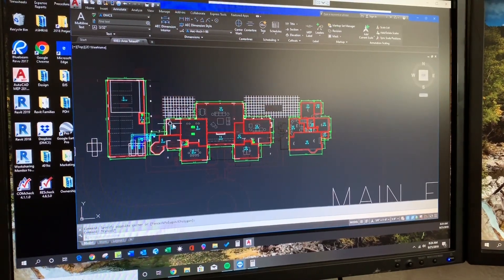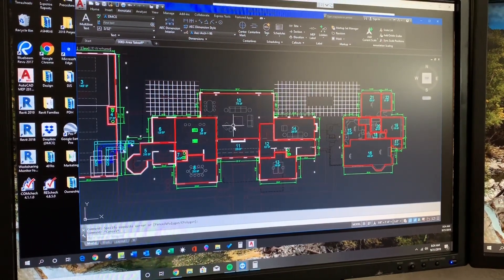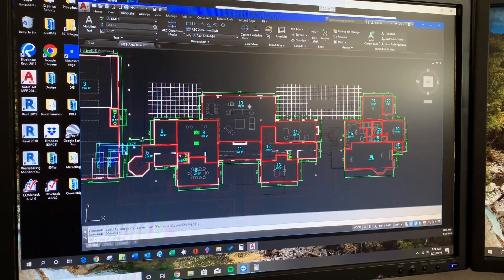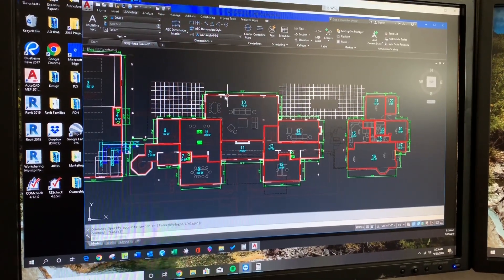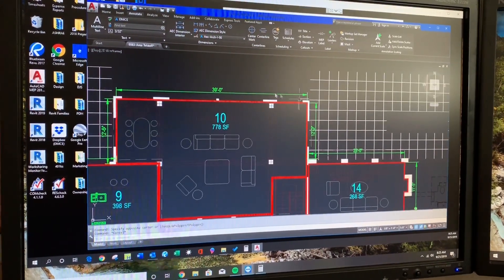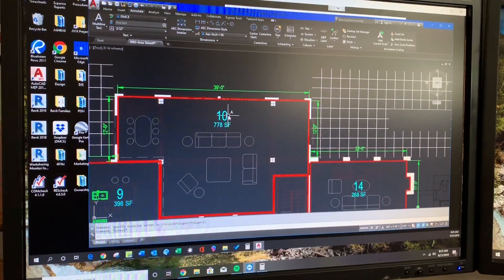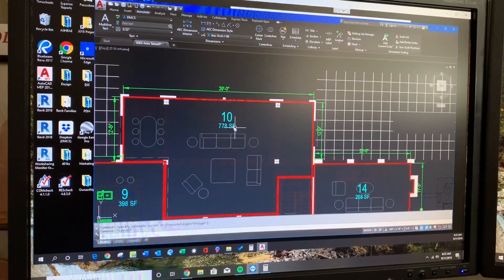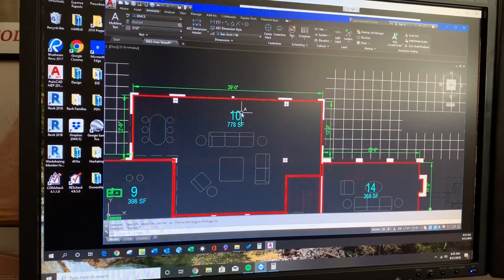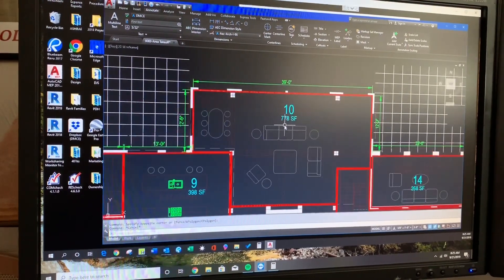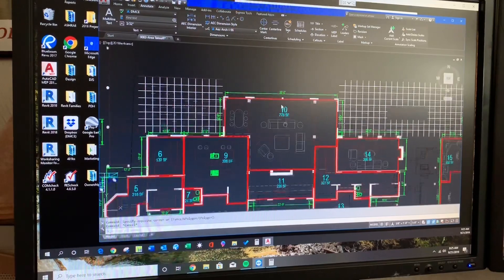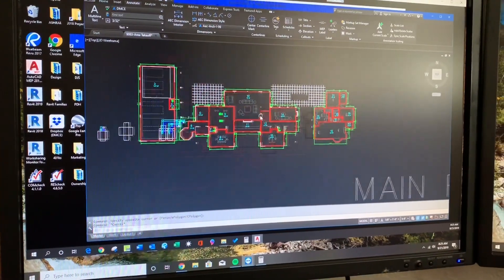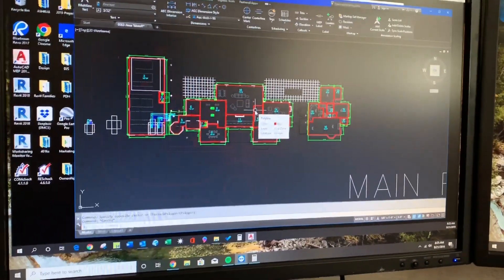Basically a zone is a thermal control area. So you take the perimeter square footage and then take the exterior perimeter lengths which are in green and then the square footage which is in red. This is the living room. And then you number the zones so that you can track it in your load calculations. So just a very repetitive process.